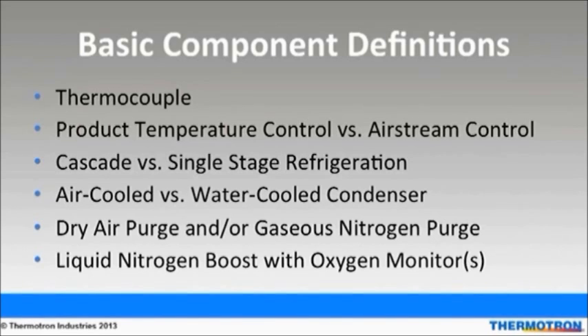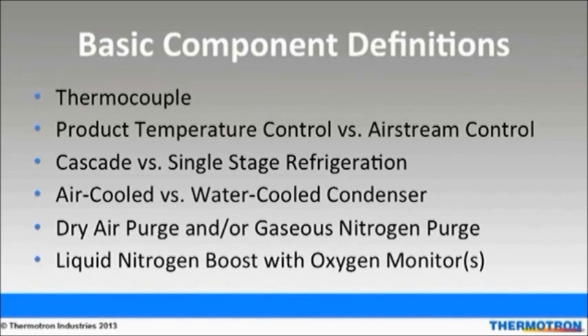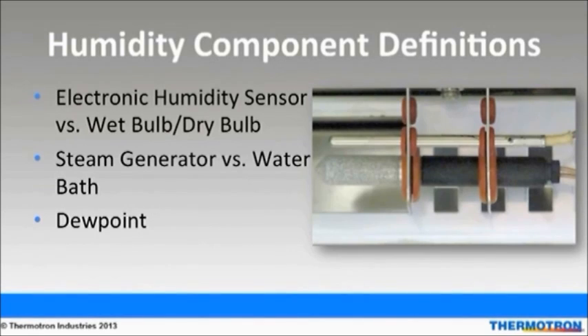Gaseous nitrogen is an alternative to dry air purge. Its purpose is to minimize the moisture level inside the chamber. Liquid nitrogen boost enables faster pulldowns and dissipation of heat from the product. An oxygen monitor or monitors can be added to the chamber or test lab to monitor oxygen levels, and it also features an alarm if a depleted oxygen environment exists. An electronic humidity sensor gives high quality responses and is very accurate at low humidity levels, and it doesn't require as much maintenance as a wet bulb-dry bulb system.